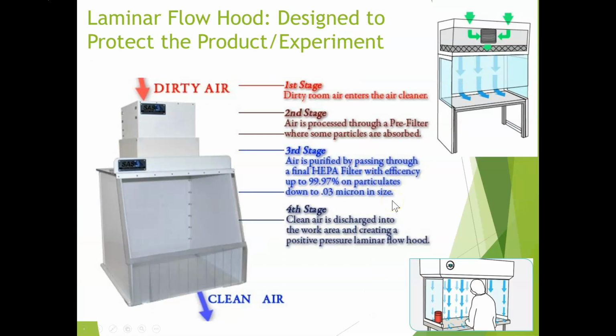The most simple tissue culture hoods are laminar flow in design. These push filtered air out towards the experimenter, away from the work area. This design maximizes the protection of the cells in the work area. You can see in this diagram that unfiltered air is drawn in at the top and then passes through a series of filters before being discharged down into the hood space and pushes out towards the experimenter.